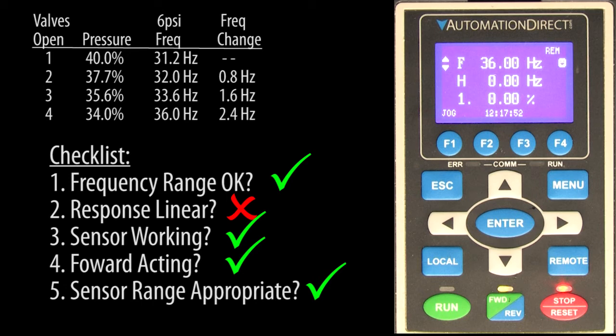We can make that work, but it's much harder to set up PID and the lack of resolution will make it more difficult for PID to maintain an accurate output. So make sure your sensor's range is appropriate for your feedback signal.